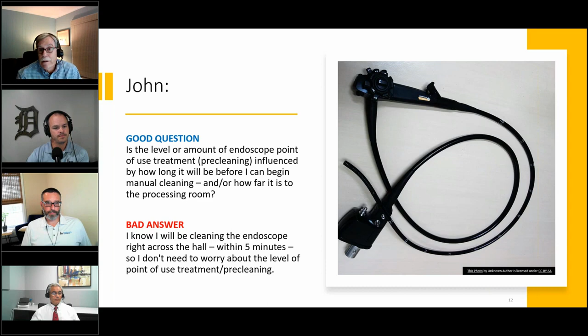Pre-cleaning needs to follow the prescribed steps in the IFUs, regardless of how many steps away your processing room is, regardless of whether processing occurs within 5 minutes or 30 minutes, regardless whether it's you yourself or somebody else that's going to be processing the scope. On this slide, you see example of contents from various IFUs for recent generation endoscopes. Pre-cleaning needs to occur as soon as possible after withdrawal of the scope from the patient.